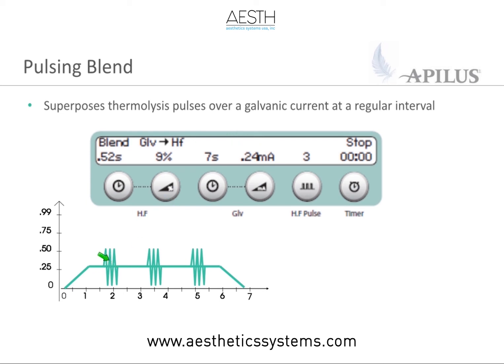Then what we have is high frequency. High frequency is thrown in there just to agitate the galvanic, not to coagulate. We can see what those settings are because they will be on the machine also. We have 3 pulses of 9% high frequency that are half a second in length, so 0.52 seconds, 9%. Anything below about 15% on this machine will not coagulate in this kind of time. So we're not coagulating. We are simply heating up the tissues and agitating the galvanic. So what we have here is 3 pulses of high frequency and galvanic current.